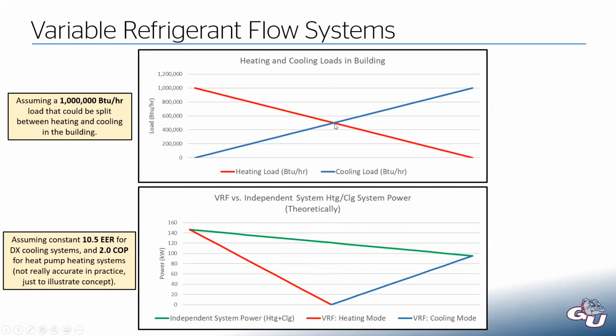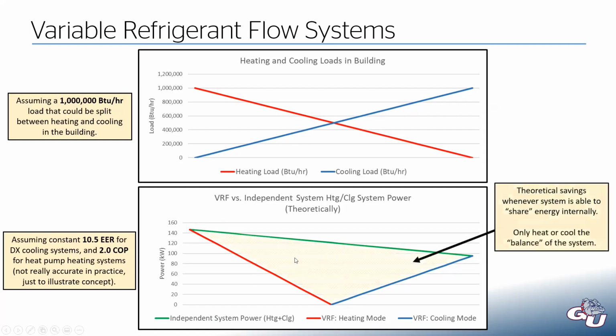In theory, if we have this perfect balance right here, we don't need to run the heat pump at all. And so that's why this zeroes out. And you also notice the VRF in heating mode. On this side of the graph, we are only running in heating mode, even though we still have cooling, but we can do that because of the energy sharing, and vice versa on the cooling side. And so the area underneath here, or within this triangle, so that would represent some theoretical savings.